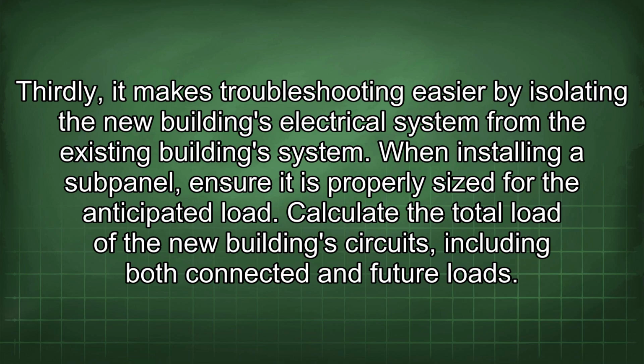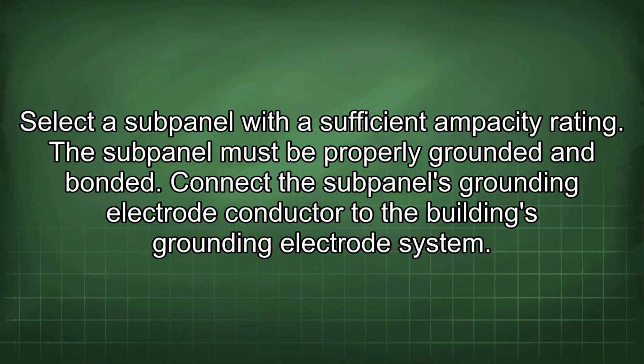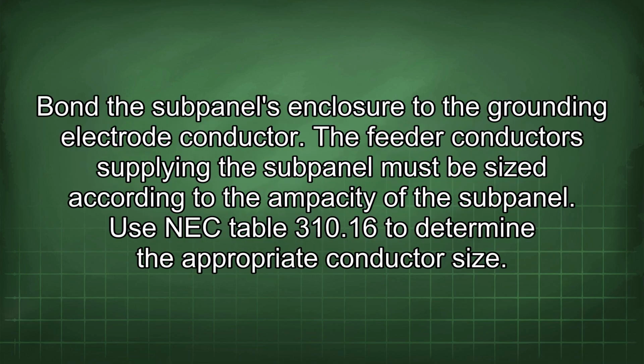When installing a subpanel, ensure it is properly sized for the anticipated load. Calculate the total load of the new building circuits, including both connected and future loads. Select a subpanel with a sufficient ampacity rating. The subpanel must be properly grounded and bonded. Connect the subpanel's grounding electrode conductor to the building's grounding electrode system. Bond the subpanel's enclosure to the grounding electrode conductor.